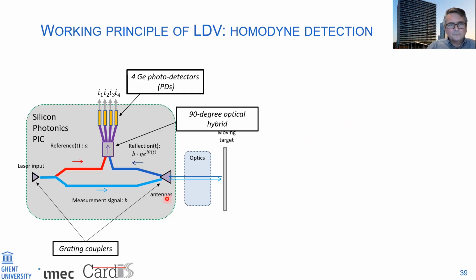We are building silicon photonics-based chips for that, in which we have a chip where a laser is hybridly integrated here. Light splits into two arms. One arm is imaged through a lens system onto the skin. Reflected light comes back and is then recombined with the reference arm. And then we have a so-called optical hybrid. That's a little detail here. But eventually, in a set of detectors, we can measure the phase change essentially between the two arms, and that is changing because the skin here is moving back and forth upon each heartbeat.